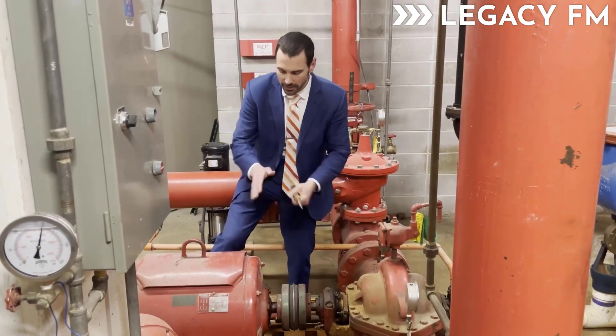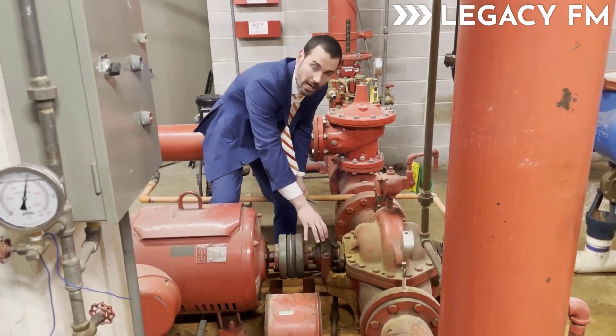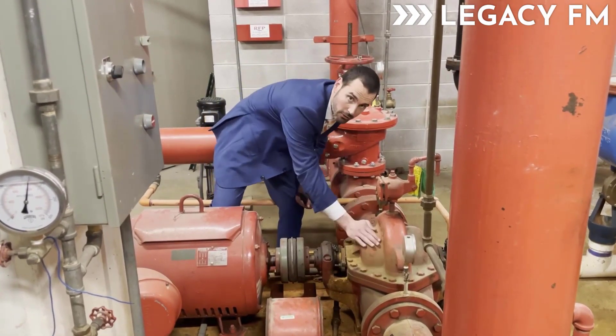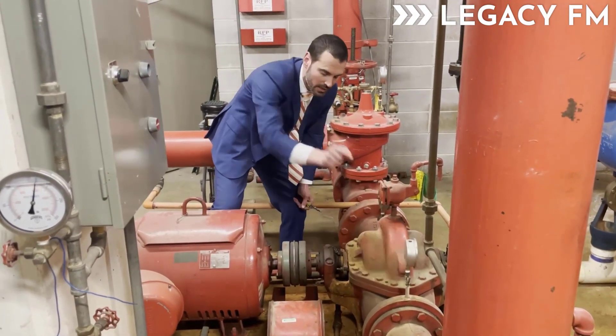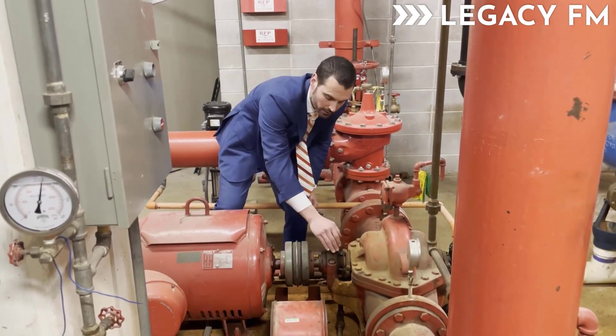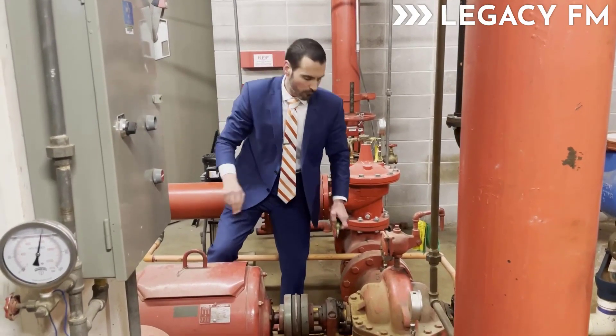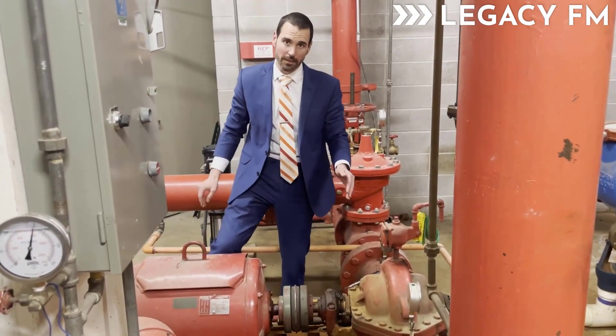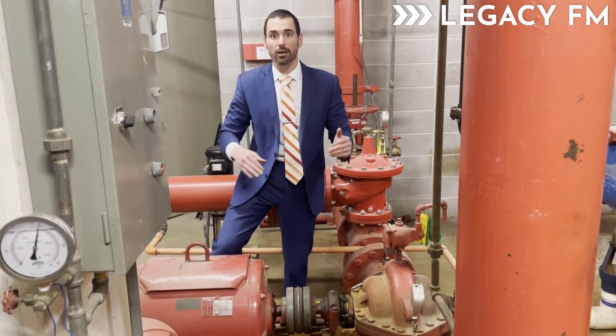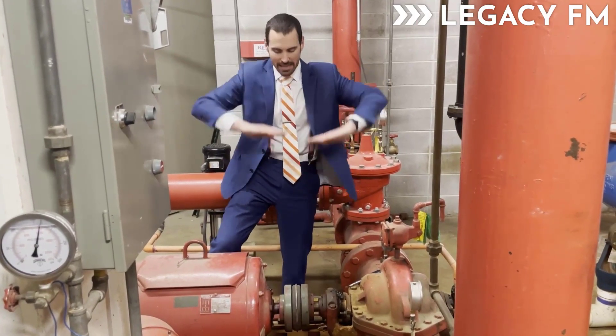Annually, the fire pump shaft is required to be checked against the motor shaft. This is our fire pump right here — the fire pump shaft coming into a coupling. This is our impeller area that actually boosts part of the pressure. This is the shaft for the impeller.